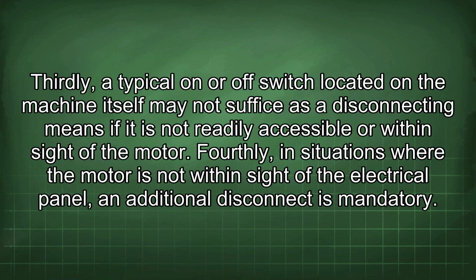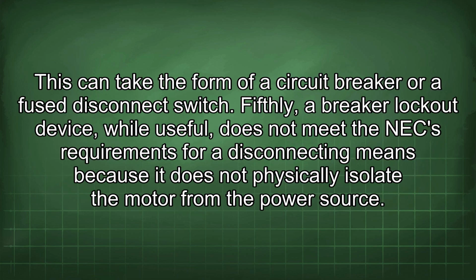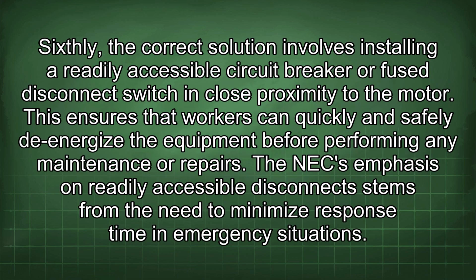Fourthly, in situations where the motor is not within sight of the electrical panel, an additional disconnect is mandatory. This can take the form of a circuit breaker or a fuse disconnect switch. Fifthly, a breaker lockout device, while useful, does not meet the NEC requirements for a disconnecting means because it does not physically isolate the motor from the power source. Sixthly, the correct solution involves installing a readily accessible circuit breaker or fuse disconnect switch in close proximity to the motor. This ensures that workers can quickly and safely de-energize the equipment before performing any maintenance or repairs.